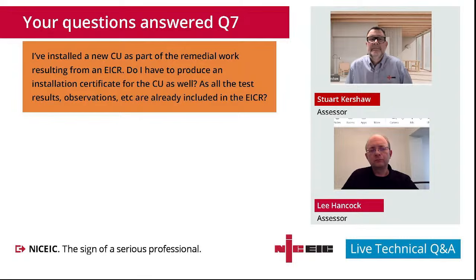Again, a common question that we get is, I've installed a new consumer unit as part of the remedial work resulting from a periodic inspection. Do I have to produce an installation certificate for the consumer unit as well, as all the test results, observations, etc. are already included on the EICR? What's our thoughts there? Can I get away with not doing an EIC?